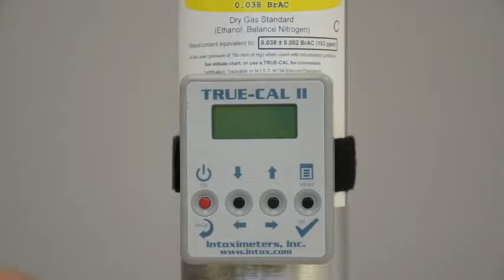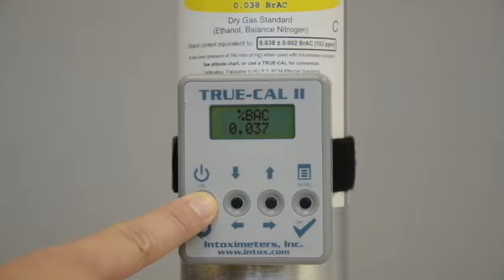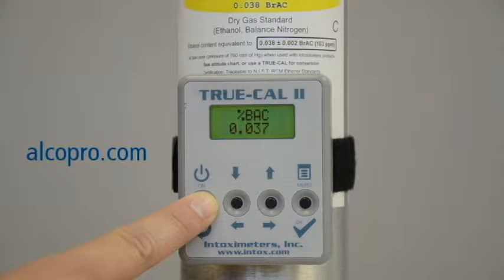You can also derive the expected value by using a TruCal device, which uses atmospheric pressure to predict the expected value of the gas. You can purchase a TruCal device at alcopro.com.